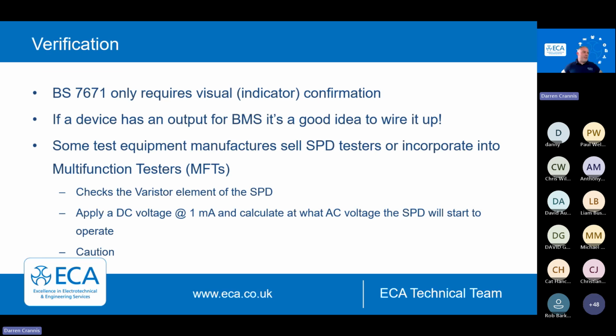Verification. So how do you test an SPD? These are all tested in factory according to the product standard. In BS 7671, we only require a visual confirmation. These typically will have flags inside them, so a red light, green light, or depending on the manufacturer, the status window will change colour. That's all we need to do.